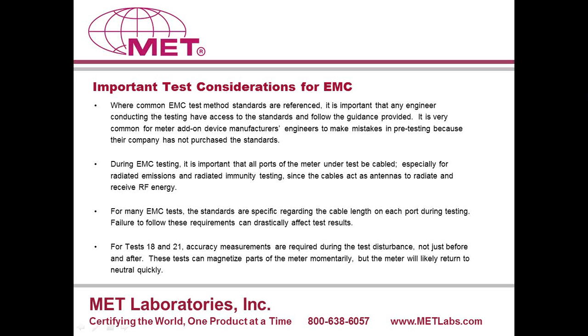Some other considerations: when you submit your samples for testing, make sure that all the ports are properly cabled because, as you know, cables act as antennas to radiate and receive radio frequency energy. Also pay particular attention to the cable length requirements that are called out in some of these standards when you submit these samples for testing. And one other thing to note is if you're doing some pre-testing on your own for test number 18 and 21, make sure that accuracy measurements are required during the test as well as after the test. These tests can magnetize parts of the meter momentarily, but the meter will most likely return quickly to its original state. So these are some of the issues that you're most likely to encounter during the EMC portion of testing.